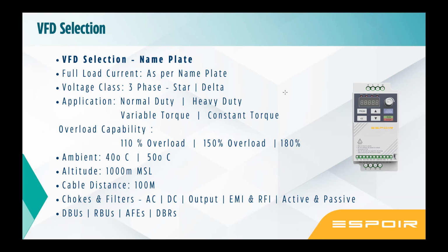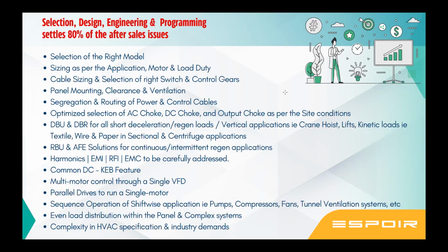Now, DBRs, dynamic braking resistors. When you use a DBU, you need to select a DBR. DBR selection is purely based on the braking cycle, the duration, and the braking torque required to be dissipated. Not selecting the proper braking resistor, again, the system can trip. The DBRs can reach their thermal limit and then they can break away. So every aspect of selection is very, very important. Whatever I explained, it is a bit in detail. I can share this presentation. You can go through it in detail, and I'm always available to explain any specific functions required over a personal call or email.